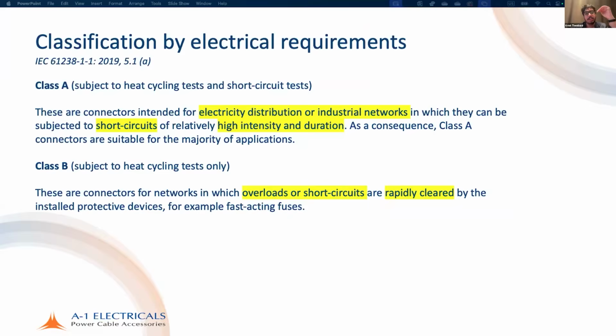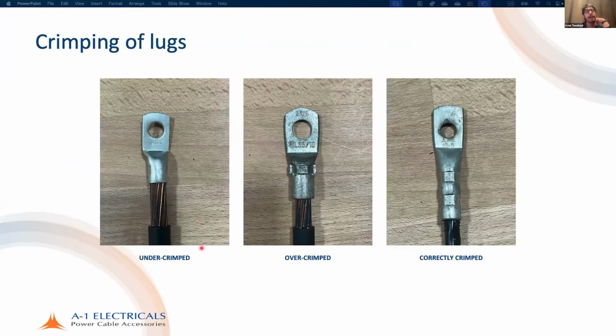Important considerations here: crimping of lugs. Under-crimped lugs are a big concern, as you can imagine. Here there is not enough crimping force applied. Over-crimped lugs, you can see these two shears on the side that have formed. The copper is just sitting there. Too much force has been applied. And correctly crimped, there is absolutely no air gap. It is a perfect seal. Yes, this is the correctly crimped lug.